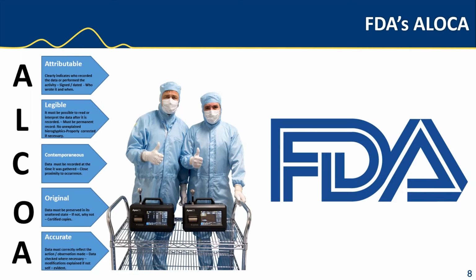It's important to remember that attribution doesn't apply only to the collection of original data, but also to any changes made to it during its life cycle, including any analytics or reporting. L stands for legible. This goes beyond whether someone's handwriting is readable or not. It means that all collected data must be a clear, permanent record, and can be read and interpreted at any time over the retention period. If data cannot be correctly interpreted, there are additional risks that come to the fore when it's reviewed for quality analysis and audit purposes.